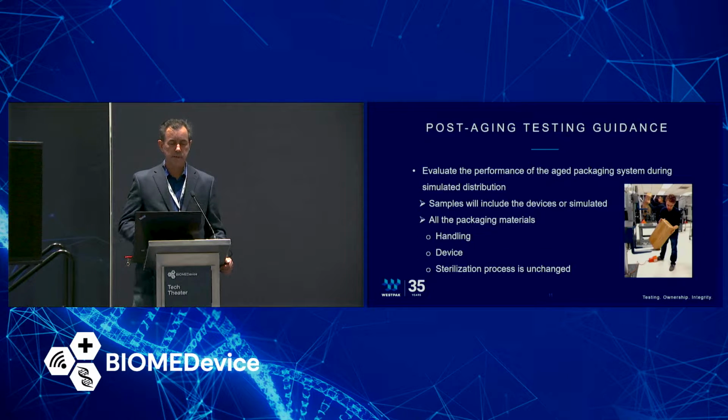Now, this is in contrast to the performance testing. This is where we're doing package performance testing. So we jump back here to the aged packaging system, where that needs to have the similar or near identical product in the package and subjected to all the stresses we talked about earlier: handling, the device, and sterilization will be the same. The sterilization process must be the same.